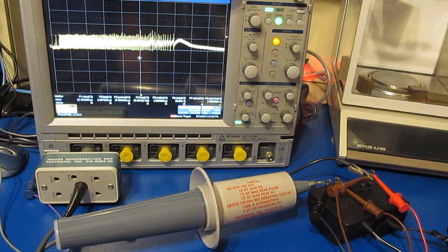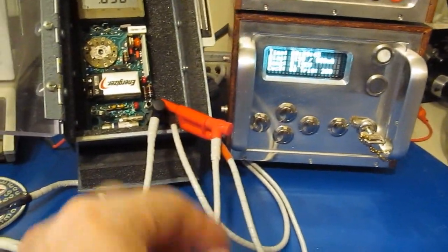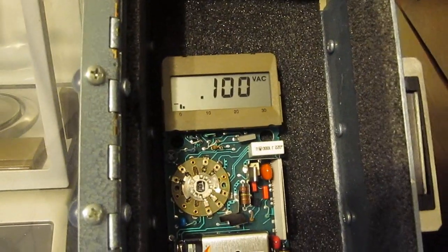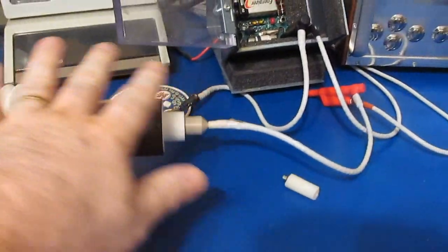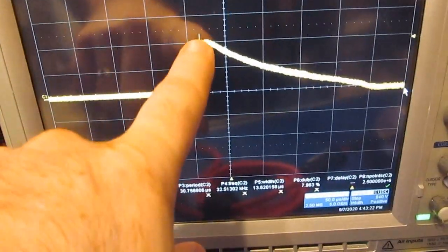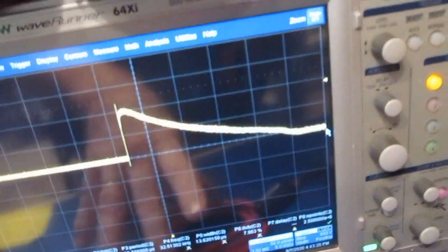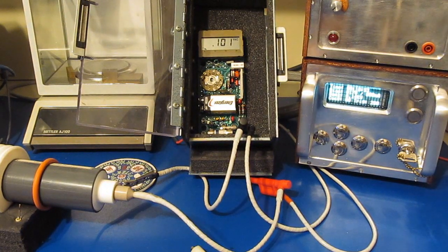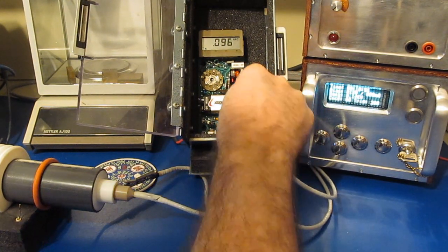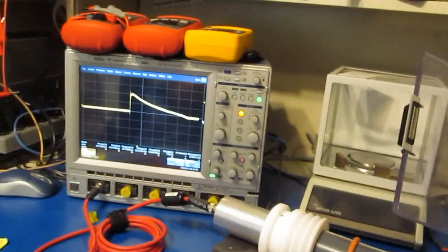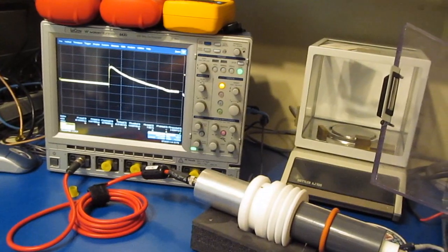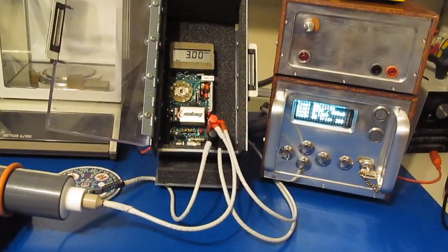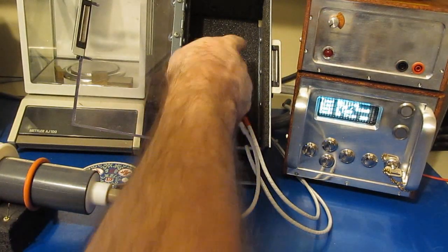So let's go ahead and we'll set up our Fluke 87. You can see I have our transient generator set up - currently it's not attached to the input of the meter. Our Fluke 87 is set to the volts AC mode, and again our oscilloscope probe is attached in parallel with the meter. And this is just going off to our LeCroy. You can see we're two divisions up or 1000 volts. This is where I start testing all the meters at. The only purpose again of the oscilloscope is just to give me some kind of an indication if the meter starts to break down. So again, this is the open circuit waveform, so the meter has nothing to do with that decay - that's all being dissipated internally at the transient generator.